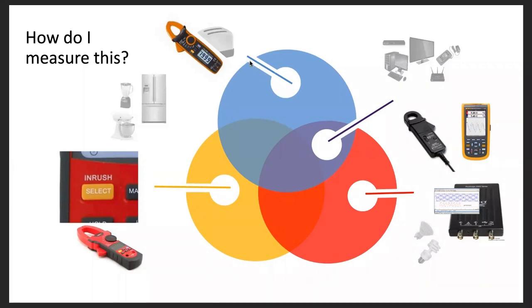A standard ammeter will measure those continuous loads. And so continuous current can be measured with most any ammeter. But also pretty common in a lot of ammeters that are available now is inrush detection. What that does is it has a max hold for that peak current when you turn on a motor, when that compressor cycles, when you open the refrigerator door. So highly recommend having an ammeter with inrush detection and learning how to use it. It's pretty simple and will definitely pay dividends.